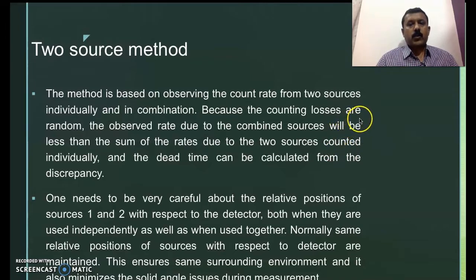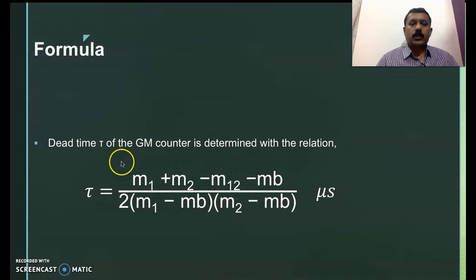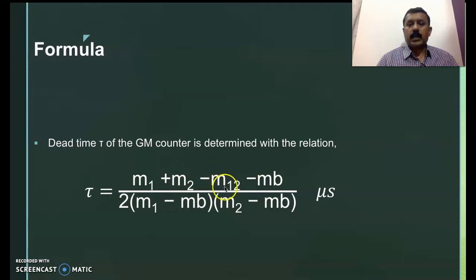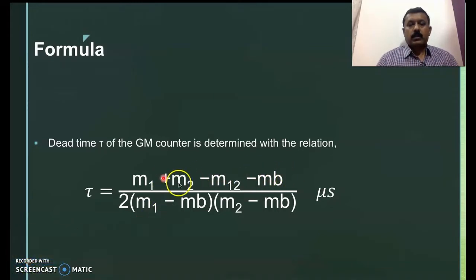We place source 1 first and take the count. We then place the second source and take the count. Then we place both sources together and measure the counts. Care has to be taken about the relative positions of source 1 and 2 with respect to the detector. The formula used to determine dead time tau involves M1 (count rate with source 1 only), M2 (count rate with source 2 only), M12 (count rate with both sources), and Mb (background count). Tau is generally expressed in microseconds.